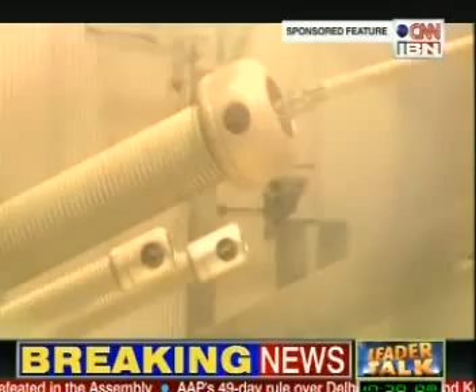On the left side, you can see the bushing from the converter transformer, where the AC output goes out to the network. The complete valve hall is surrounded with aluminum cladding to prevent radio noise from escaping. The environment inside is maintained slightly pressurized to avoid dust coming inside.